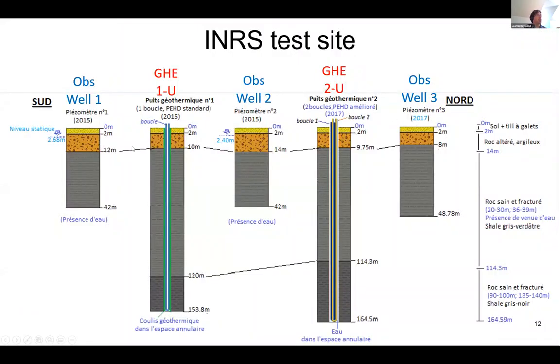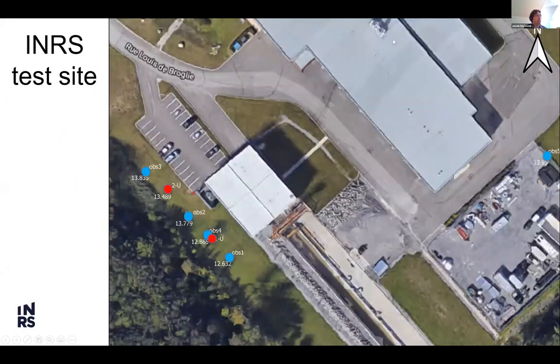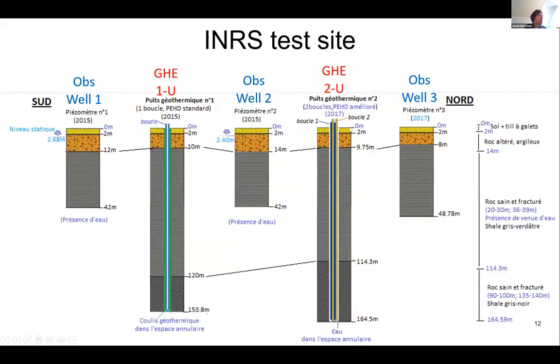This is basically the stratigraphy that we have at the site. It's not a very ideal site for a geothermal heat pump system, although this building that is shown here is heated and cooled with geothermal heat pumps, and the ground heat exchangers are under this parking lot. The ground is more or less 10 to 15 meters of silty overburden, followed by a shale that doesn't have a very high thermal conductivity, so it's not ideal for heat exchange, but that's the ground we have, and it's fine for a geothermal heat pump system.